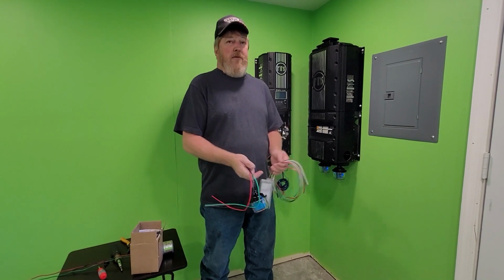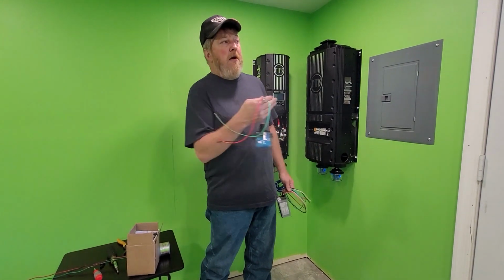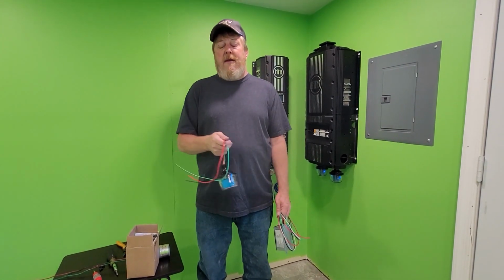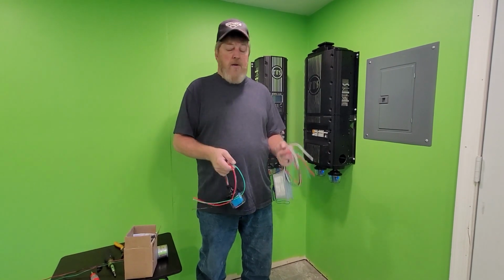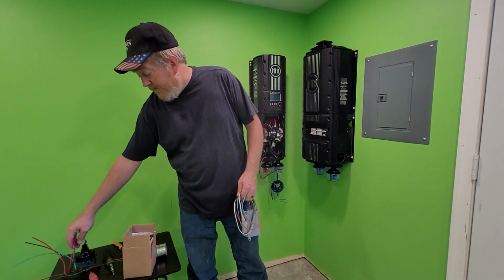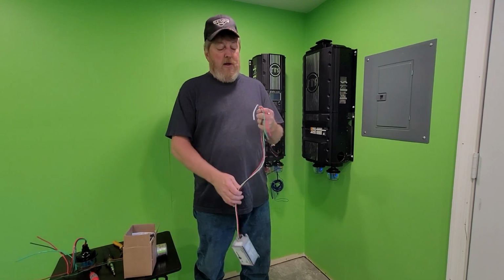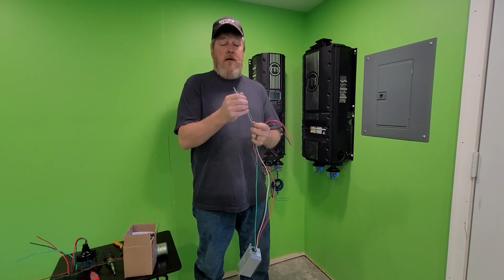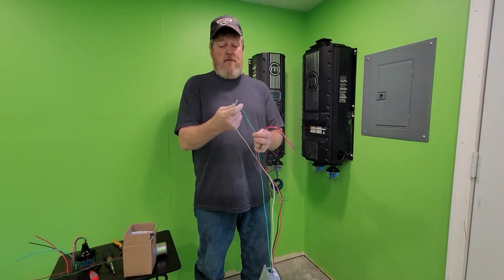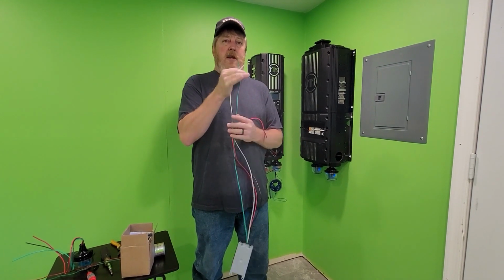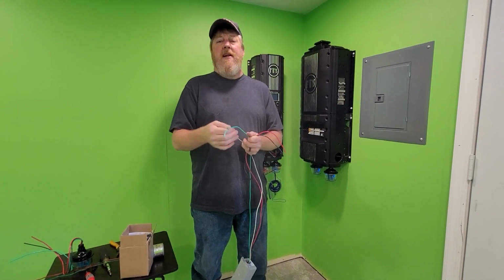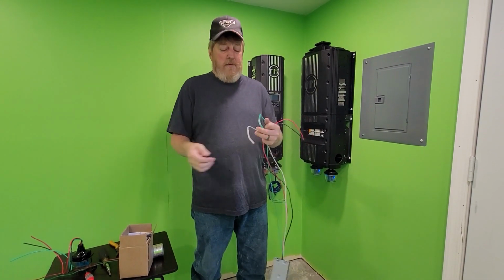So in this example we're using out here, we're about 40 feet from our main panel. You may ask, why do you want a white wire? Your white wire and your green wire in the US and Canada are bonded together with a hard bond somewhere in your main electrical panel, your main electrical service, your system if you will.